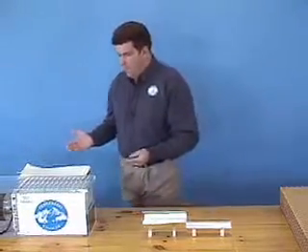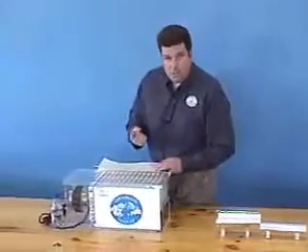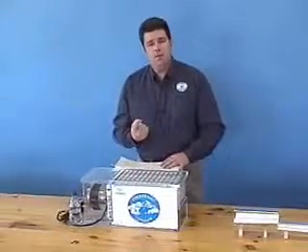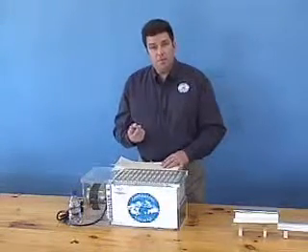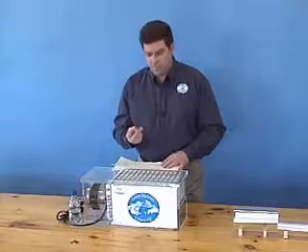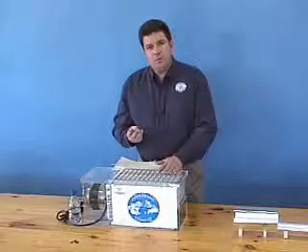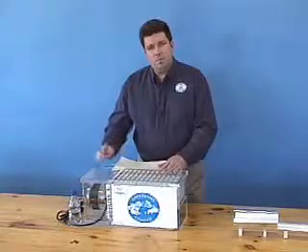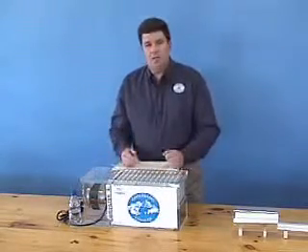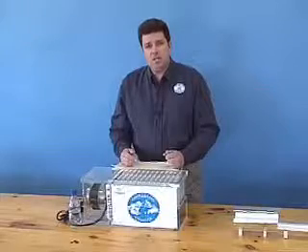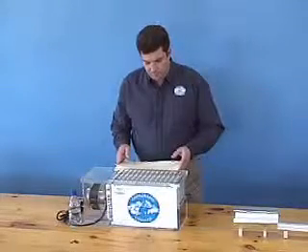But Coolerado coolers have a small pressure drop loss, less than 1-inch column of water. We only throw away about 50% of the incoming airstream, and we can cool toward the dew point temperature of the incoming air. With this knowledge, you can begin to understand the pure genius of the Maisotsenko cycle.